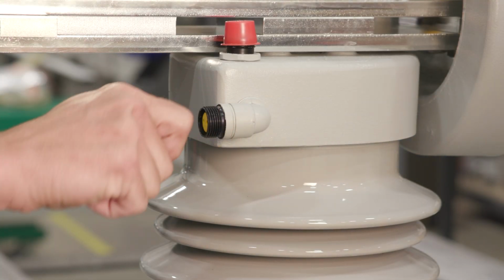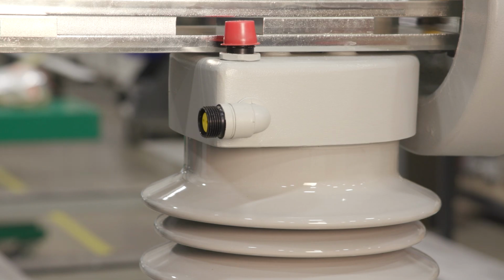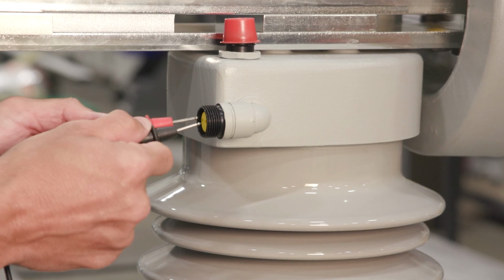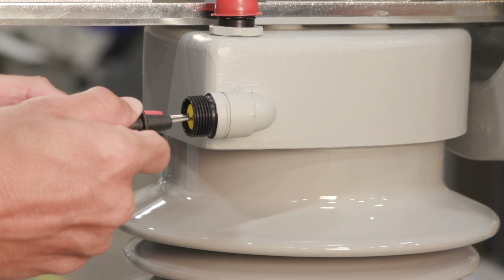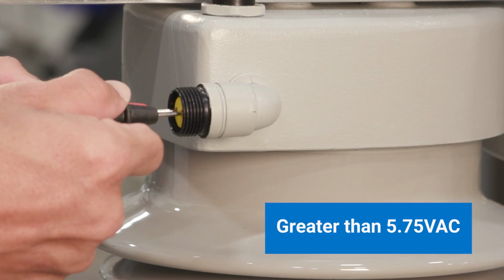Now remove the caps on the control power elbow fitting on the high voltage side of the IT. Record the output voltage of each transformer, which should be greater than 5.75 VAC.